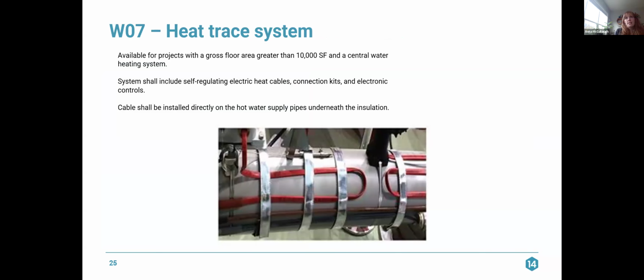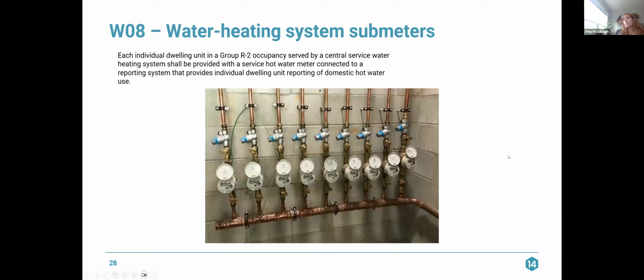W07 is a heat trace system. So this is only available for projects with a gross floor area greater than 10,000 square feet, and they must have a central water heating system. Systems shall include self-regulating electric heat cables, connection kits, and electric controls. And the cable has to be installed directly on the hot water supply pipes underneath the insulation to keep that water warm.